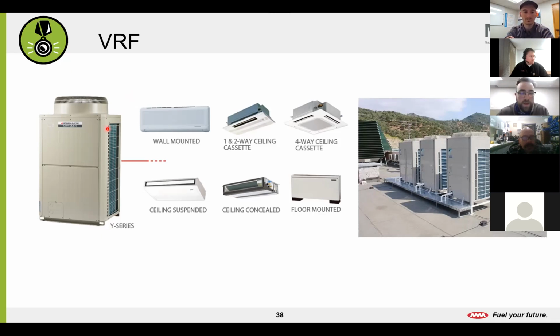So we'll have an outdoor unit. Depending on the capacity, we may have 1, 2, 3, 4 units tied to one system. It just depends on what our implementation, our application is for our building. From our outdoor unit here, obviously we have to send our refrigeration piping to our indoors. Each space or zone, as we covered in our last class here, is going to be supplied with some kind of indoor unit that handles our heat exchange and our airflow throughout the space. Our indoor units can really be broken up into 2 classifications, and that's going to be kind of exposed or concealed.